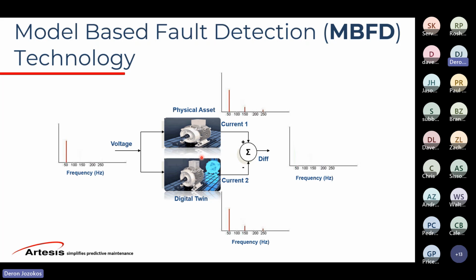And the system now knows exactly what it should look like. We measure what it actually looks like. We filter out any of those harmonics from the voltage supply. And the only thing left causing faults now are these actual defects from the machinery. Okay, so we have a PSD, the power spectral density, very similar to an FFT spectrum. So we're able to identify these faults, and our system actually uses the same exact fault frequencies that all the bearing manufacturers use with vibration.